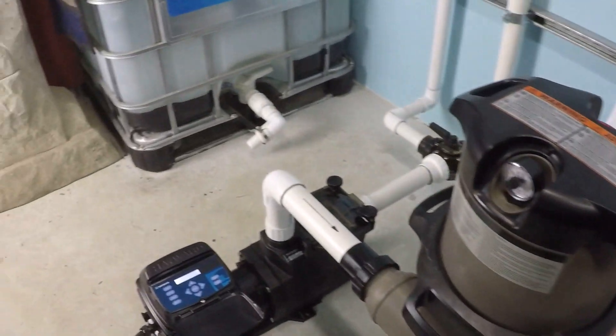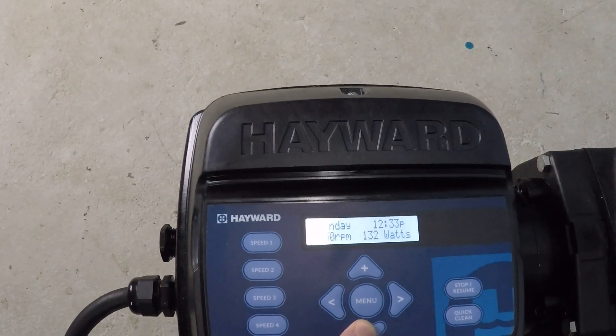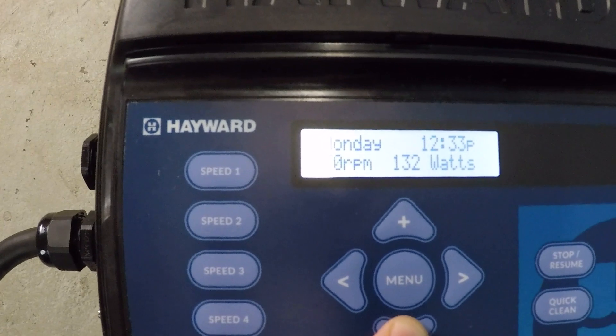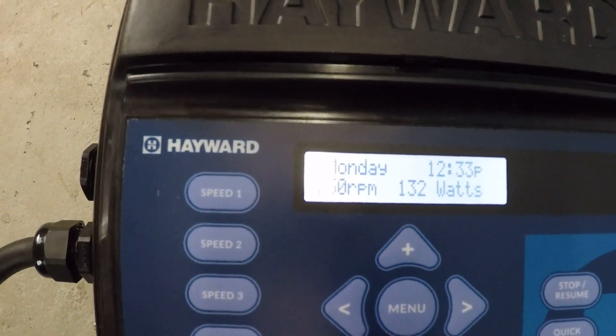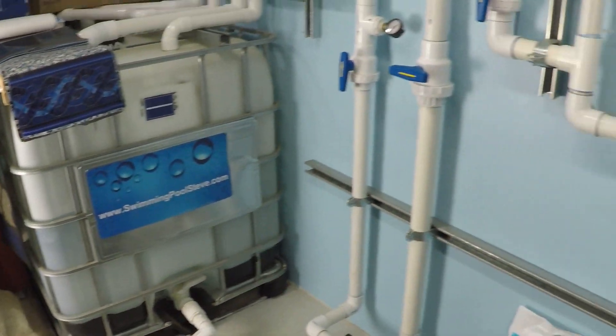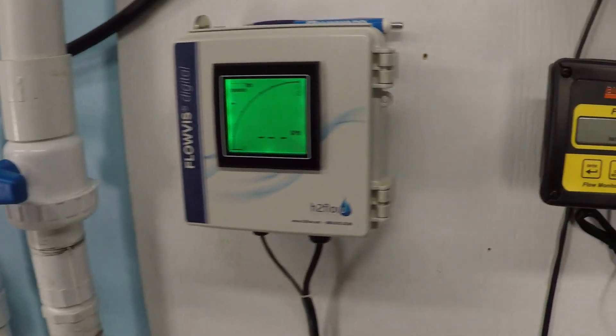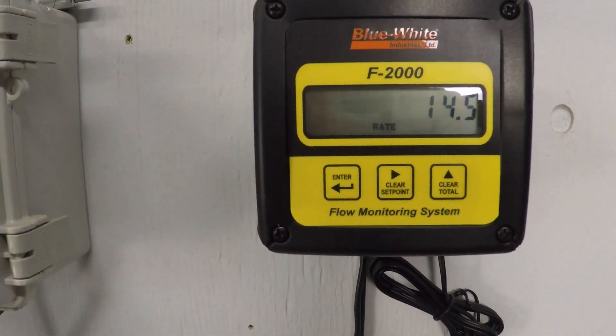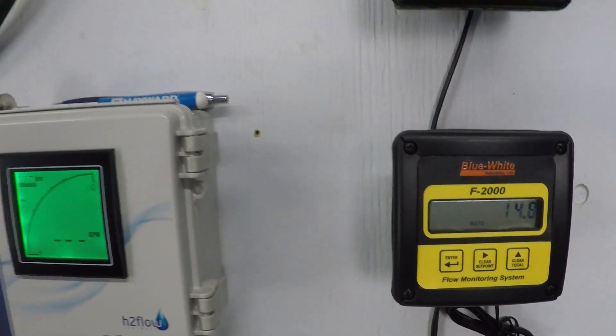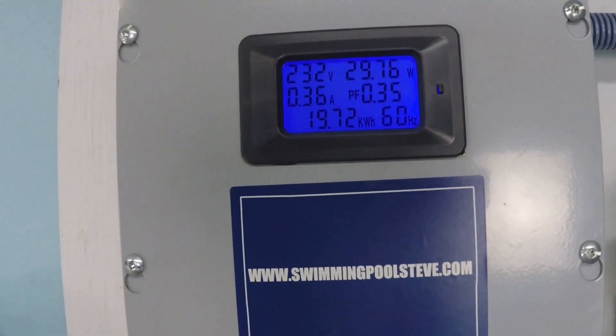Like, let's take a look at this really low RPM here. 750. It's so low, it's so quiet, you wouldn't even know if you're moving any water, unless you had a flow meter. You definitely want a flow meter. I can see that we're moving quite a bit of water here, about 14.8 gallons per minute. Look at that power consumption.